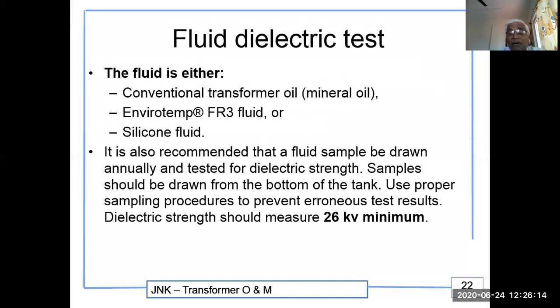While taking the sample, if half a liter is required, take a bottle of half a liter only. First, put a small amount of oil and rinse the bottle inside and throw away that oil, and then collect the sample oil up to the neck, full, without leaving any air on the top of the bottle.